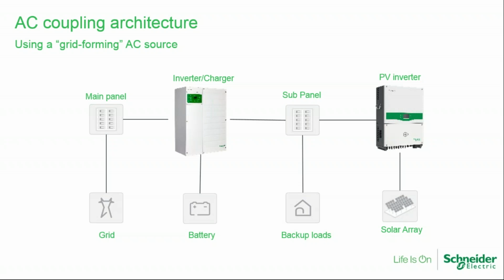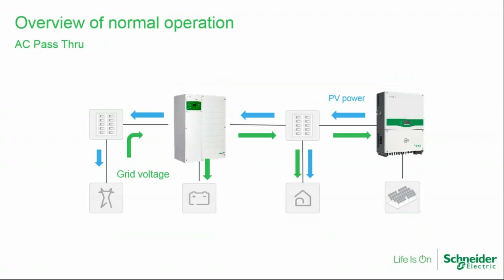And this is an example of using the inverter as a grid former. So as long as there's PV available, or as long as there's grid available, the grid passes through the internal transfer switch in the inverter, goes to the sub panel. The PV inverter sees that as a reference and provides current back to the loads and to the grid, basically as long as the grid is there. And so we can see here that the grid voltage can charge the batteries, it can run the loads, depending upon how much load it is. If there's plenty of PV power, then it runs the loads and is sold.